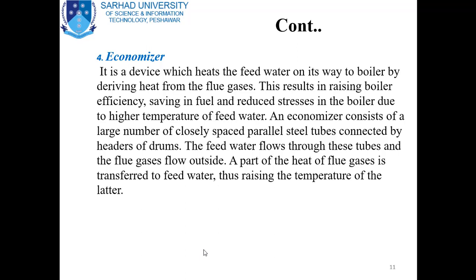An economizer is a device which heats the feed water on its way to the boiler by deriving heat from the flue gases. This results in raising boiler efficiency, saving in fuel, and reducing stresses in the boiler due to the higher temperature of feed water. An economizer consists of a large number of closely spaced parallel steel tubes connected by headers or drums. The feed water flows through these tubes and flue gases flow outside, transferring heat to the feed water.